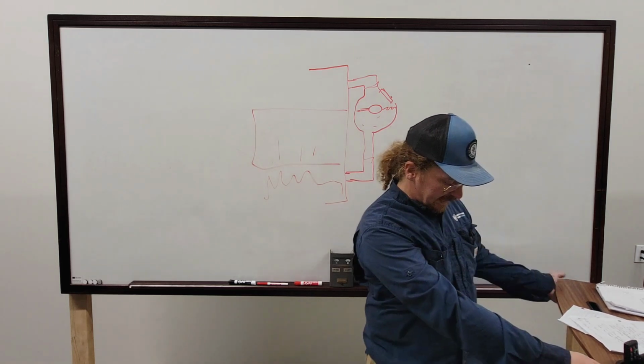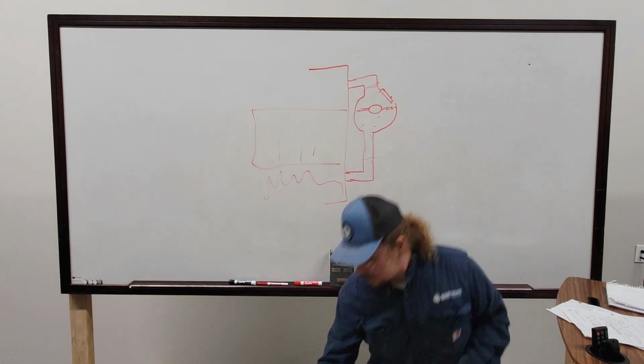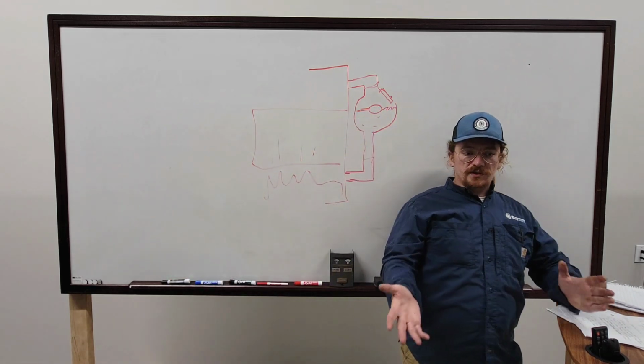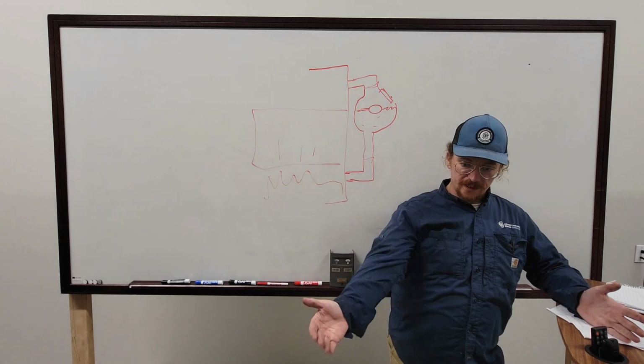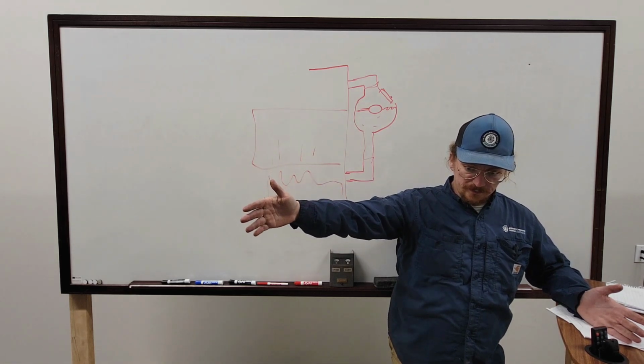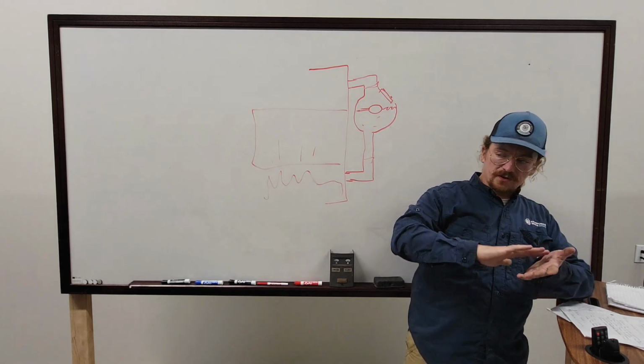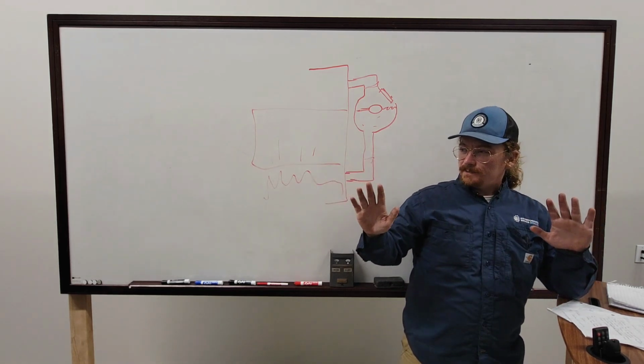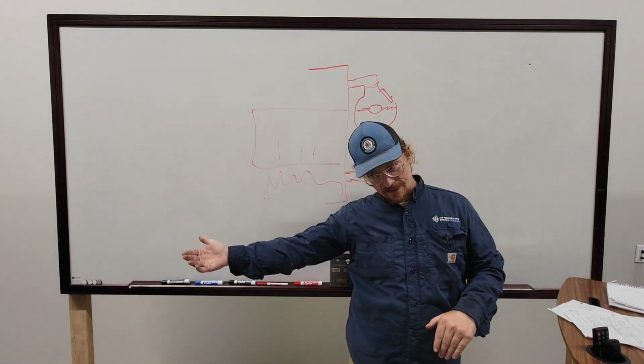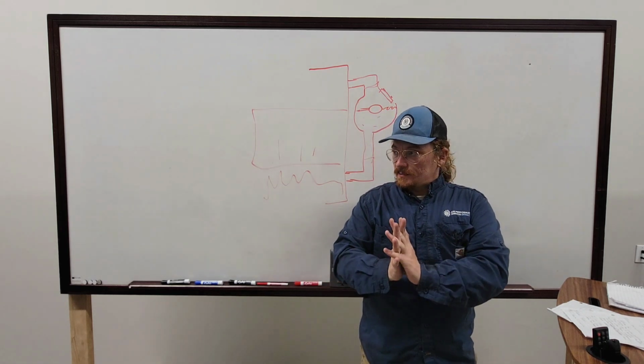It's kind of dependent because, if we're heating up water to heat up a loop, say using that water for water source heat pumps, that's condenser water that we're dealing with. So in this, we want to maintain a loop temperature of, say, 75 to 95. But our boiler is going to, so there's going to have to be some interplay there. Our boiler is going to probably produce 140 degree water that's going to mix with this 60 degree water. And then that combined water temperature is going to need to be a certain temperature.